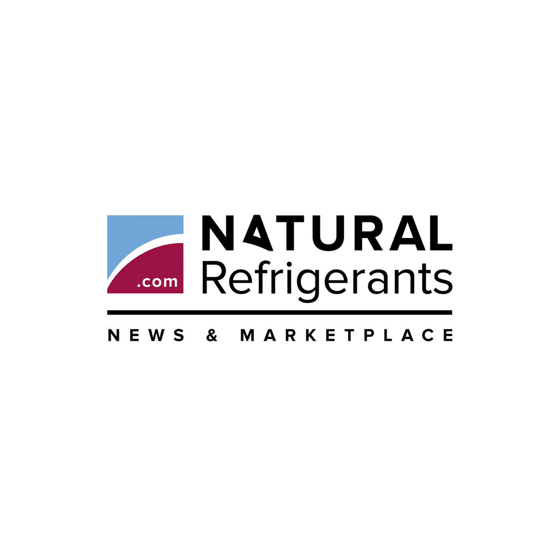Beyond efficiency, the approach adopted at Skybox Houston One is extremely simple in design, resulting in low upfront costs and enabling easy scaling, Thijsbert said. It can work with any type of server and at higher process fluid temperatures, he noted. By integrating the immersion tanks directly with the facility's evaporative cooling system, BAC's design also reduces the data hall footprint, enabling operators to maximize compute density within the same physical space. It's actually unbelievable that we're not doing this for all other data centers worldwide already, Thijsbert said.